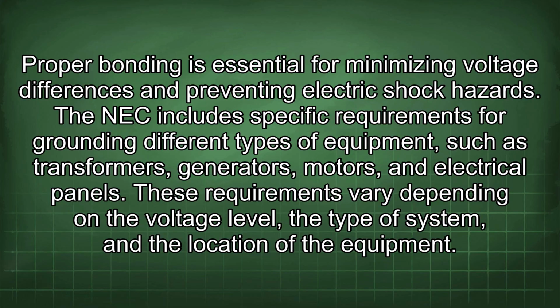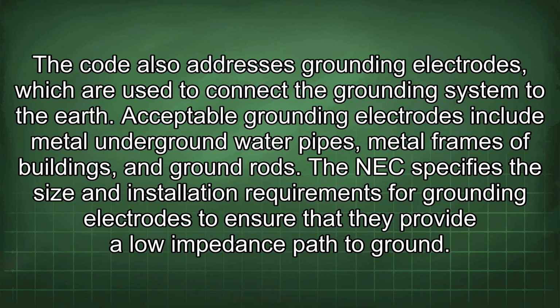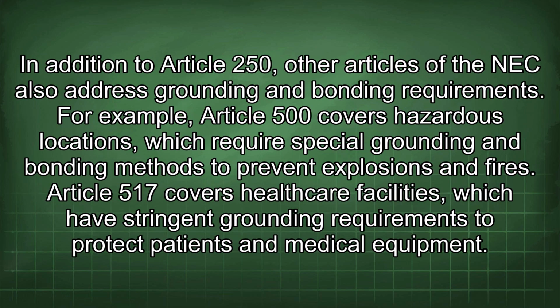The NEC includes specific requirements for grounding different types of equipment, such as transformers, generators, motors, and electrical panels. These requirements vary depending on the voltage level, the type of system, and the location of the equipment. The code also addresses grounding electrodes, which are used to connect the grounding system to the earth. Acceptable grounding electrodes include metal underground water pipes, metal frames of buildings, and ground rods. The NEC specifies the size and installation requirements for grounding electrodes to ensure that they provide a low impedance path to ground. In addition to Article 250, other articles of the NEC also address grounding and bonding requirements.